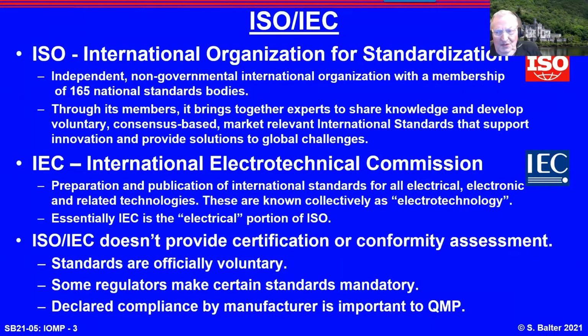The standards world really is two correlated parts, the International Standards Organization and the International Electrotechnical Commission. The part of IEC that is pertinent to medical physics is basically 62B, which is diagnostic, and 62C, which is radiation therapy. There's great misunderstanding of the roles of these organizations, and the parent organizations do not by themselves provide certification of equipment or assessment. All ISO IEC standards are voluntary. In some parts of the world, the regulators make the standards mandatory, which means they've got to be followed in great detail. A caveat in these areas: the standards are basically on equipment, not necessarily on the use of equipment.